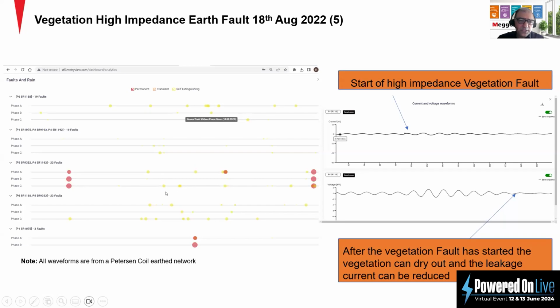And it's showing the fault log, which shows each fault that is happening in the network. For example, on this system, there is some transient fault recorded on phase C in the middle one. And if we are not looking at this one, this may cause a permanent one. That's how the smart sensors and the software are helping with pre-fault detection.